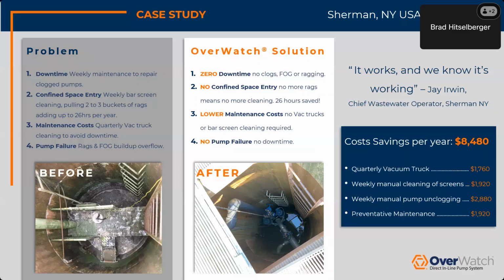And in January 2018, they decided to go with the OverWatch because in their budget, they were having to send quarterly visits from a vac truck to avoid some of the downtime. They were having FOG layers that would get so thick that they would actually take up the transducer reading, and it was causing overflows. But then they also had to do weekly bar screen cleanings that were taking up a bunch of time. So he needed something that could go in there, be a drop-in replacement, and then provide all of the solutions to those issues.